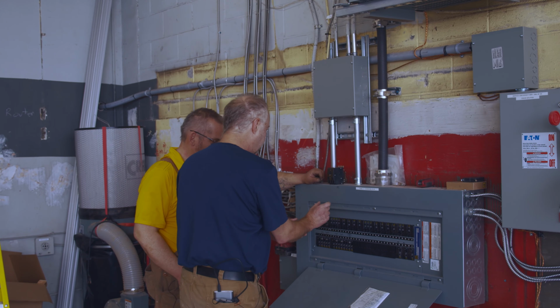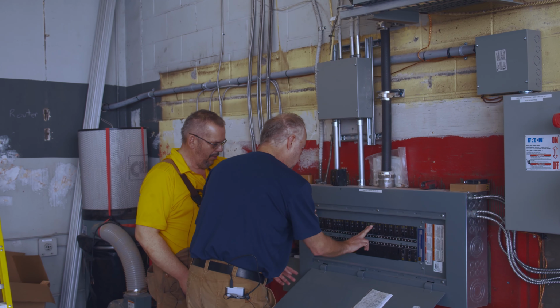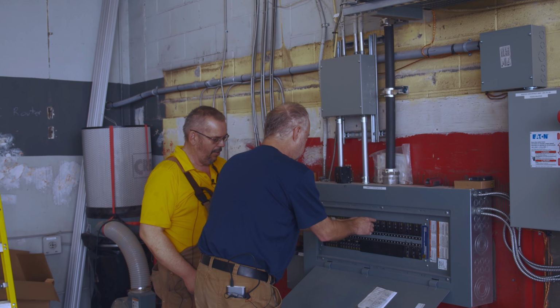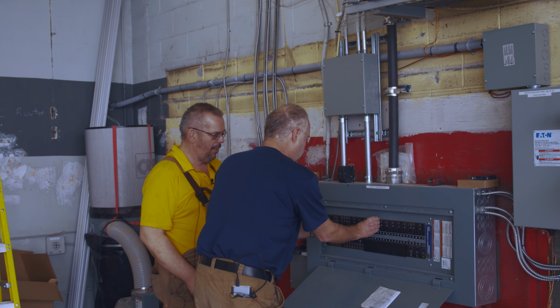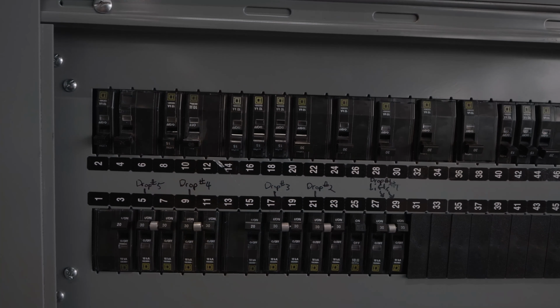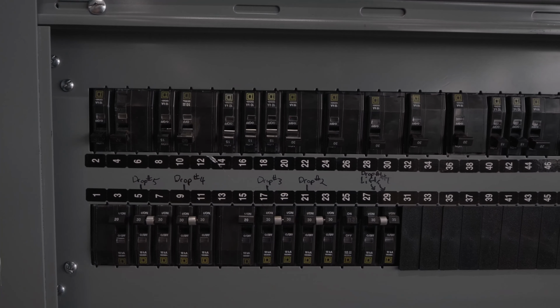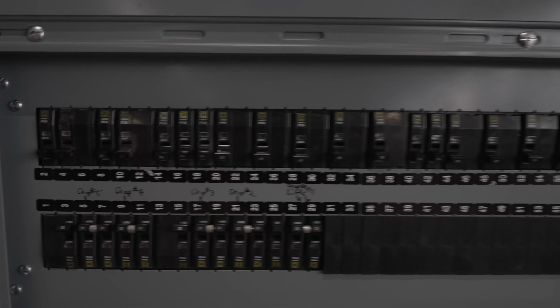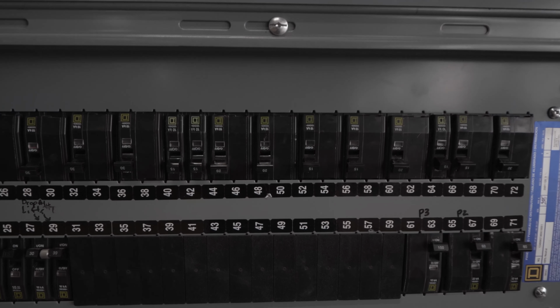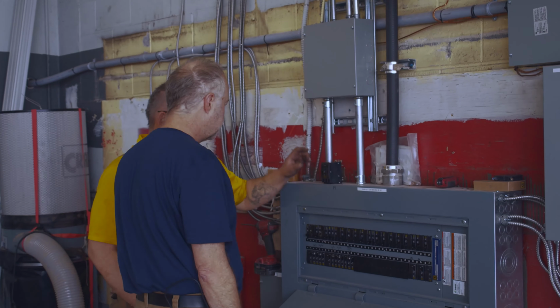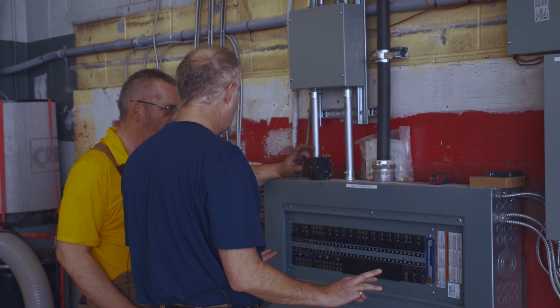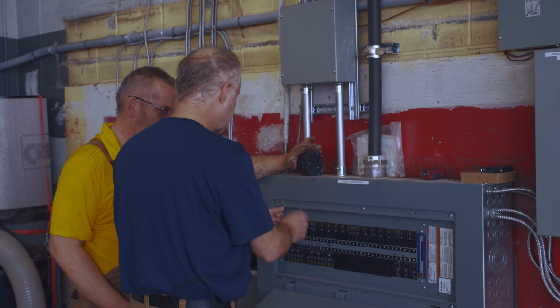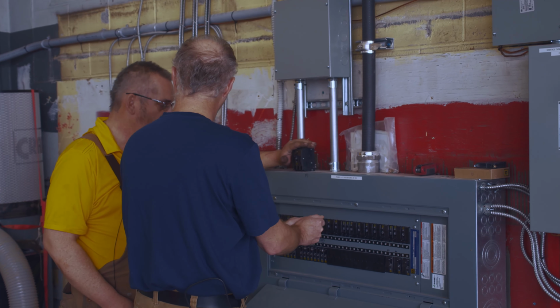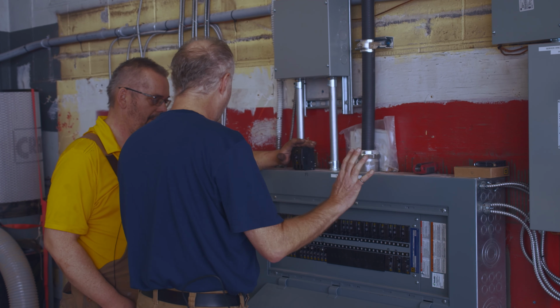Yeah. So to get your 240, you would take a pair, and then one circuit breaker would go in there, and you have your things coming out of it. It'd be a double pole circuit breaker just like the one beside it. Those are singles, and this is a double. So it has two wires going into that breaker. So here with three-phase, you use the same kind of circuit breakers. The two-phase circuit breakers will work here. Oh, absolutely. Which is kind of mind-blowing.